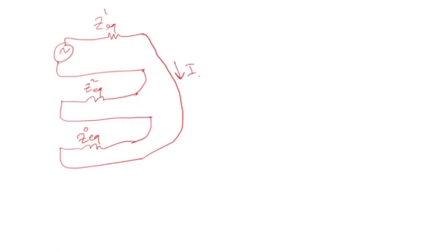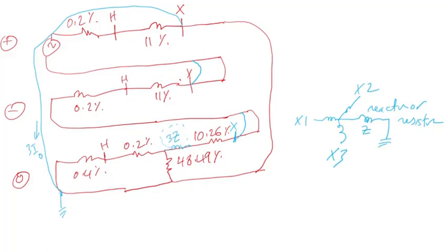What will flow here is I0, which equals I1, which equals I2 — zero sequence, positive sequence, and negative sequence currents. These flow through the equivalent zero sequence impedance, then through the equivalent negative sequence impedance, and back to the source through the positive sequence equivalent impedance. The positive sequence equivalent impedance is the high-side system impedance plus the transformer impedance, which is the same as the negative sequence impedance. For the zero sequence impedance, it's one impedance plus another in parallel with a third, all in series with another impedance.